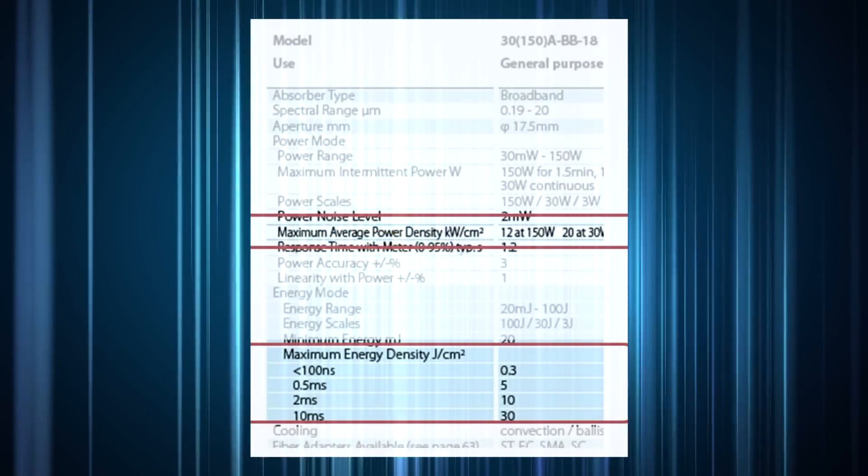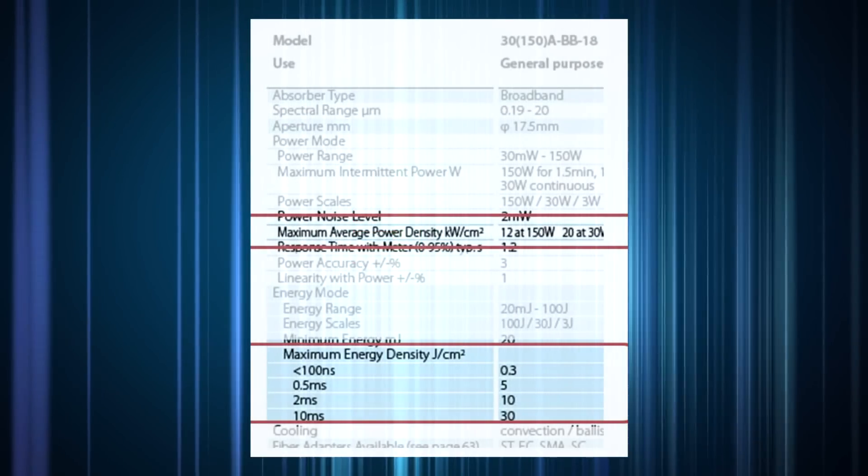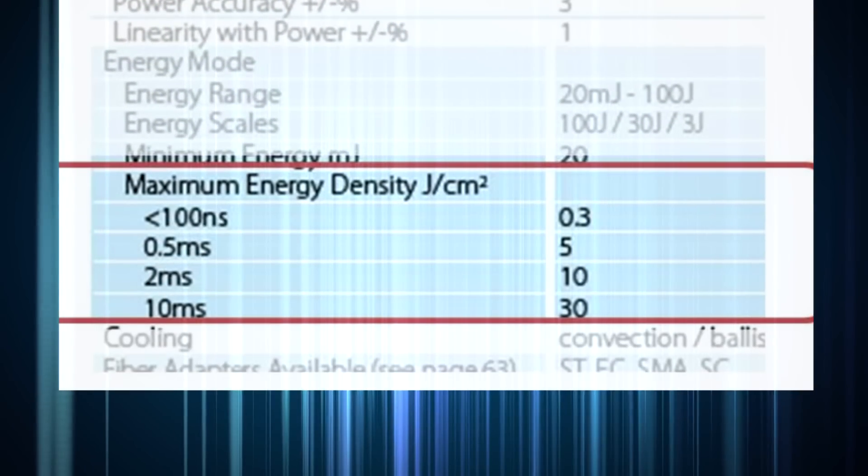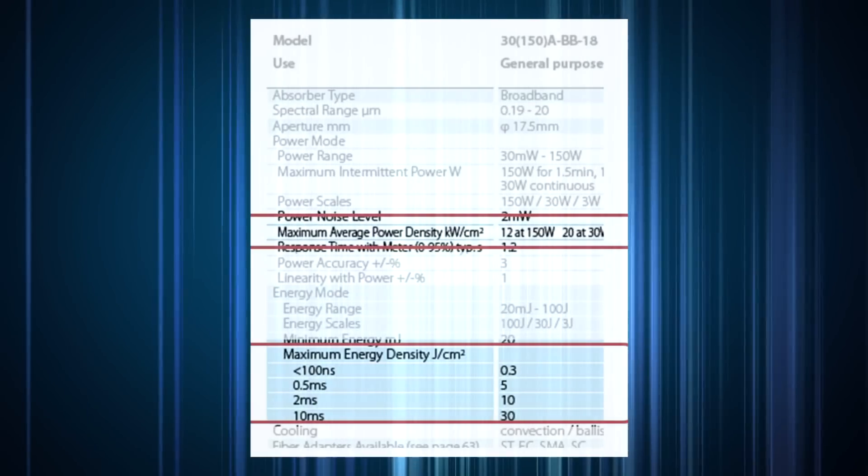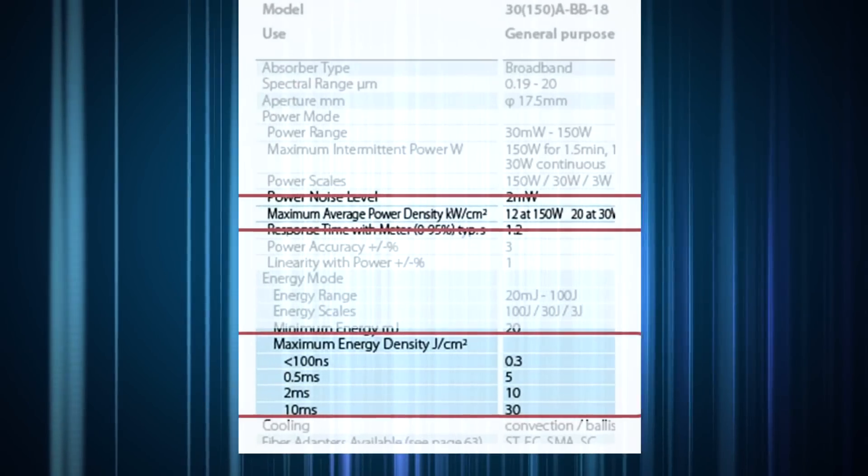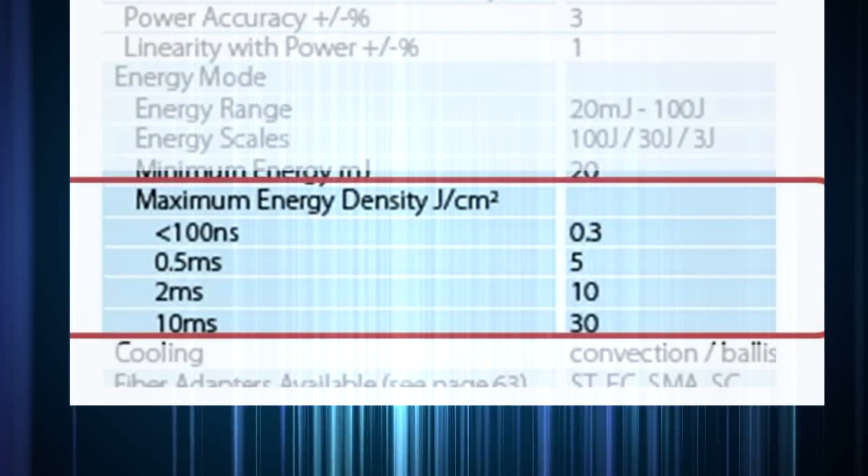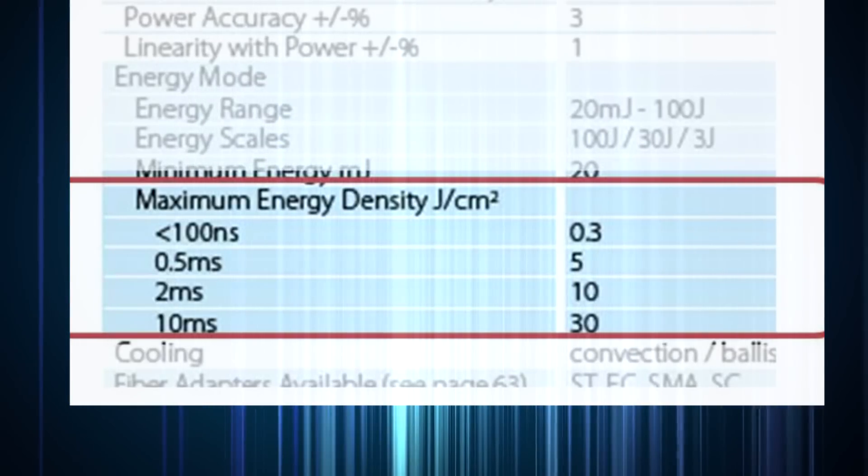If you look carefully at our sensor data sheets, you'll notice that there are two damage thresholds, maximum power density and maximum energy density. As opposed to maximum power density, which is usually a simple number in kilowatts per square centimeter, maximum energy density is usually portrayed as a table with several possible values in units of joules per square centimeter for several different pulse widths.